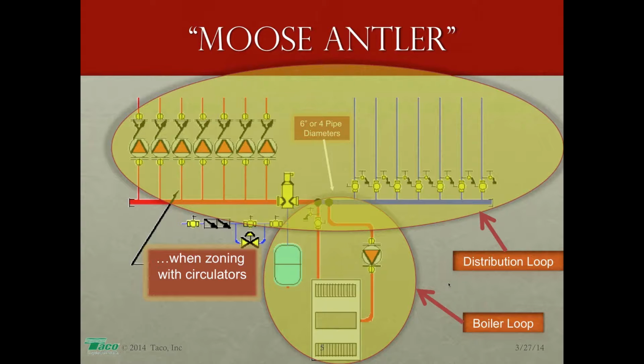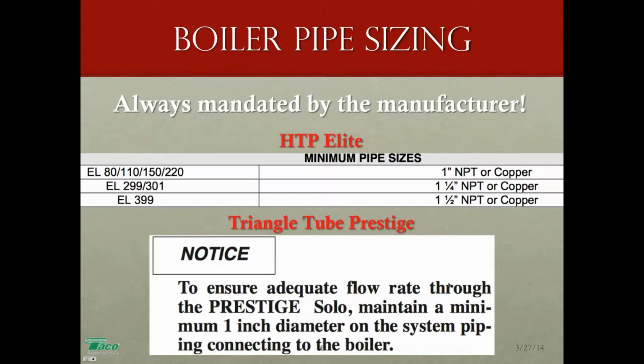Very good. Sizing the boiler piping on the boiler loop. This is really easy. You look at the instructions, it will tell you. The boiler manufacturers will tell you what that size pipe should be for the different sizes of boiler that they sell. The top chart came right out of the HTP Elite Installation Guide. For every model from the EL 80 up to the 220, they will tell you your supply and return piping from the boiler connecting to the distribution header should be no less than 1 inch. The 299 and 301, 1.25 inches, the 399, 1.5 inches.